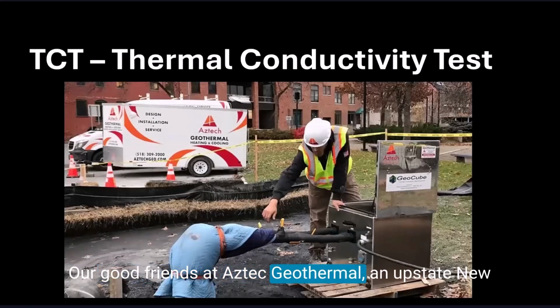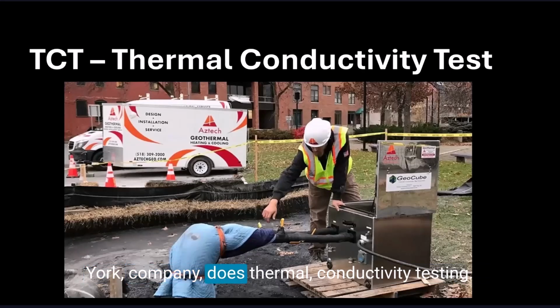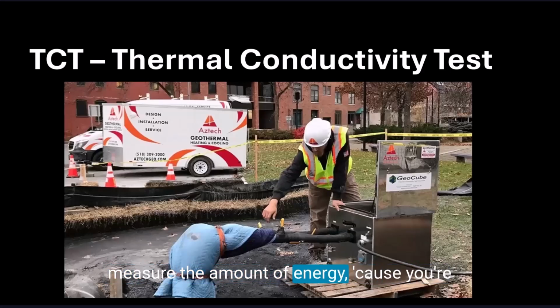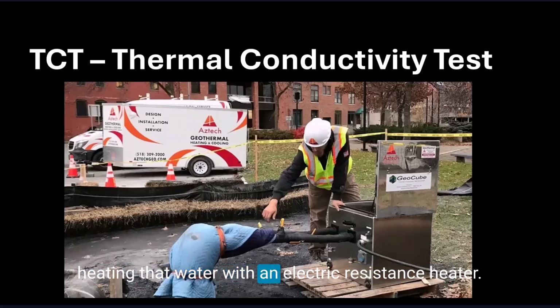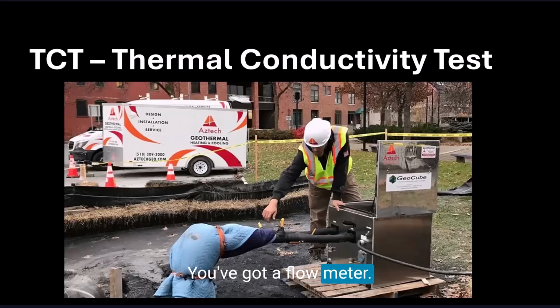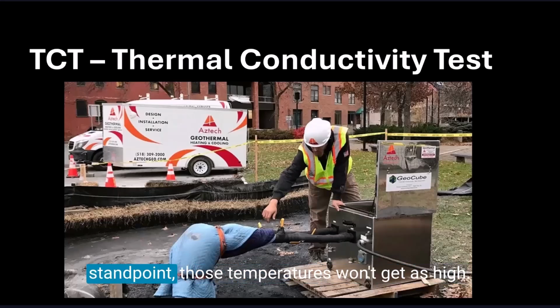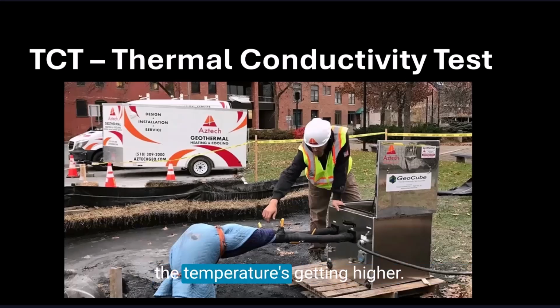Our good friends at Aztech Geothermal, an upstate New York company, does thermal conductivity testing. It's pumping heated water into the ground. You measure the amount of energy because you're heating that water with an electric resistance heater. You've got a flow meter. You're circulating that heat so you know exactly how much heat you're putting into the ground. And then you monitor how the temperature changes, typically over a 48-hour period. So if it's a very good formation from a heat transfer standpoint, those temperatures won't get as high. If it's not so good, you'll notice the temperatures getting higher.